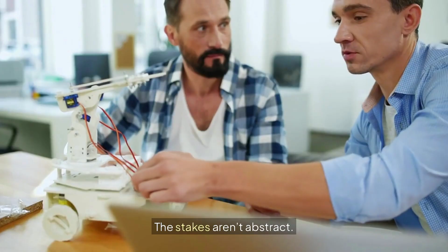The stakes aren't abstract. In data center alleys, utilities lay new feeders at a pace that felt unthinkable a decade ago. The spec might read aluminum bus in the yard, copper in the building, bimetallic transition pads at the wall. That transition is a fragile piece, 2 metals, 2 expansion rates, 2 ways to fail if a bolt stretches or a surface oxidizes. Engineers sign off because they must. There isn't infinite copper and budgets aren't bottomless. But every interface adds an if.